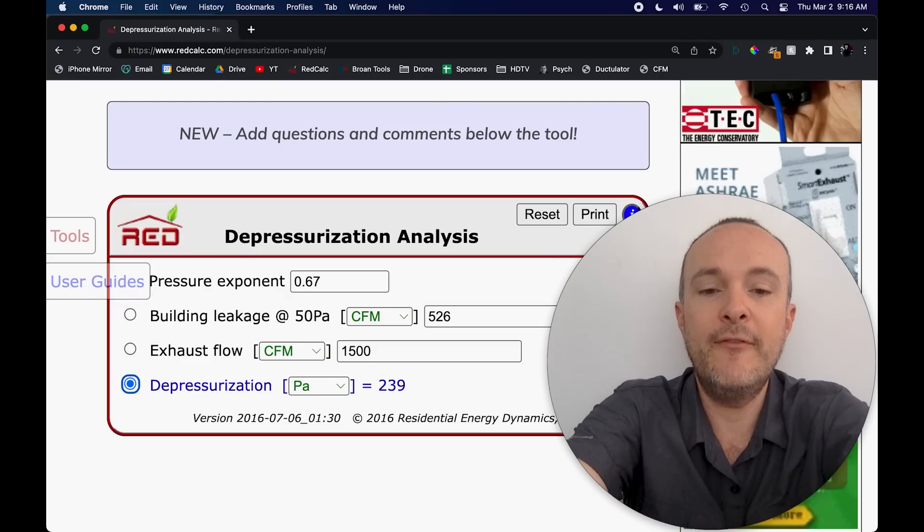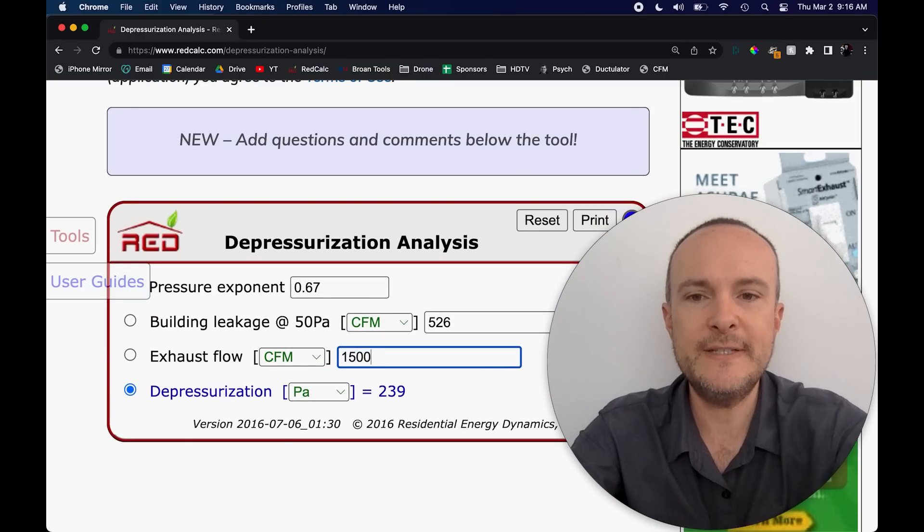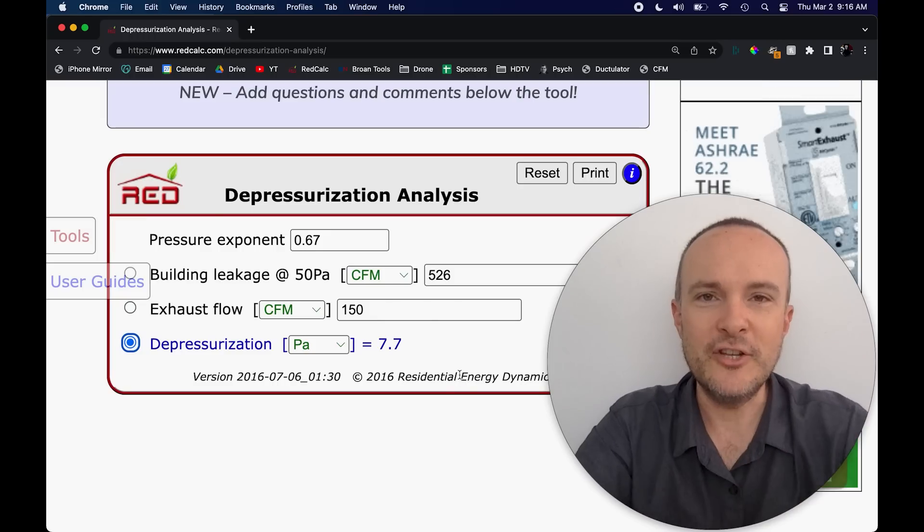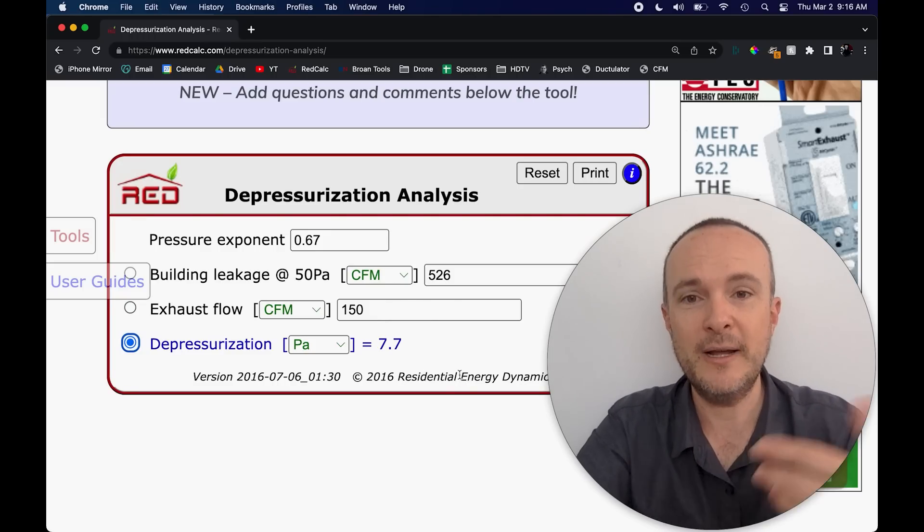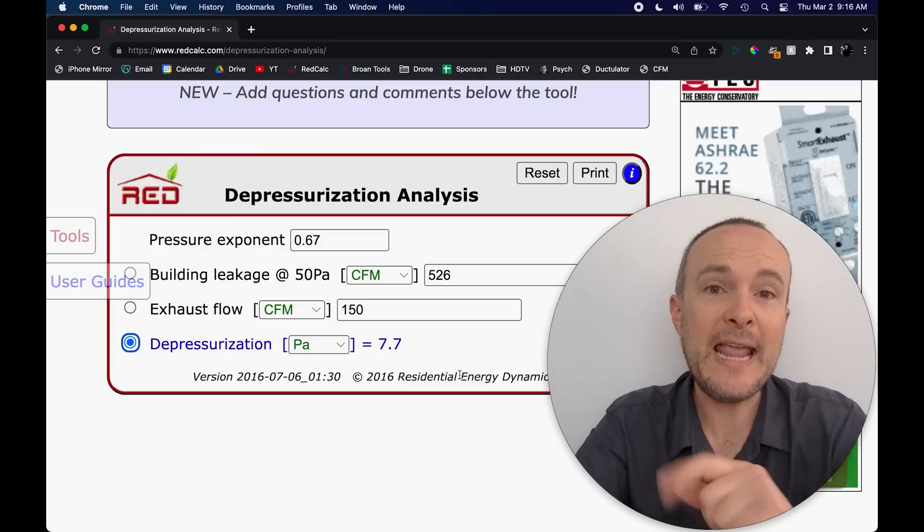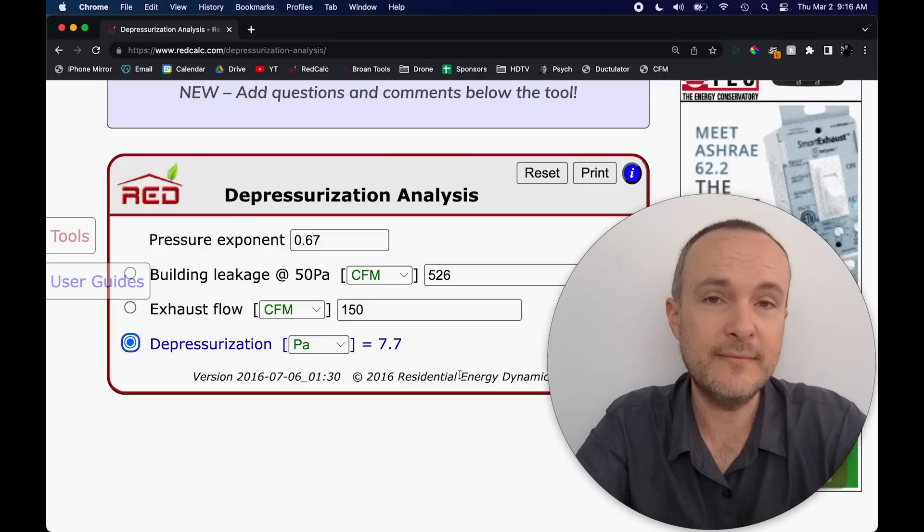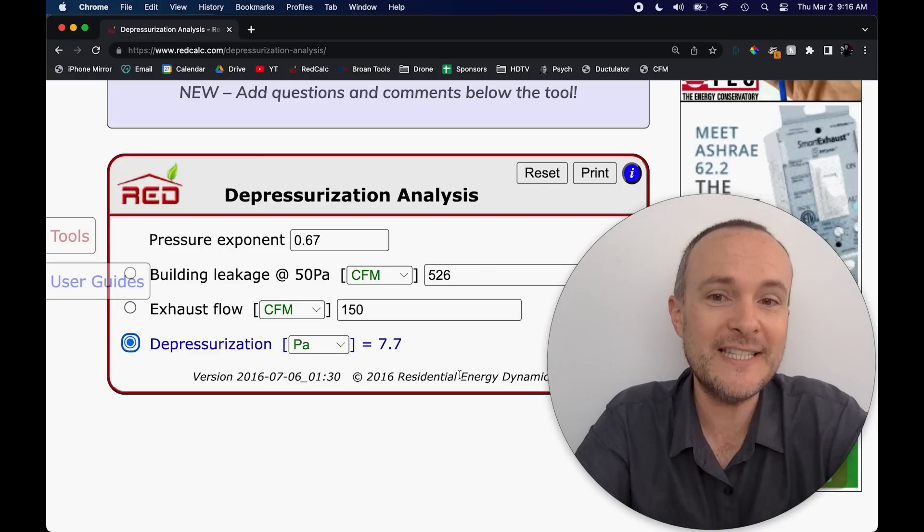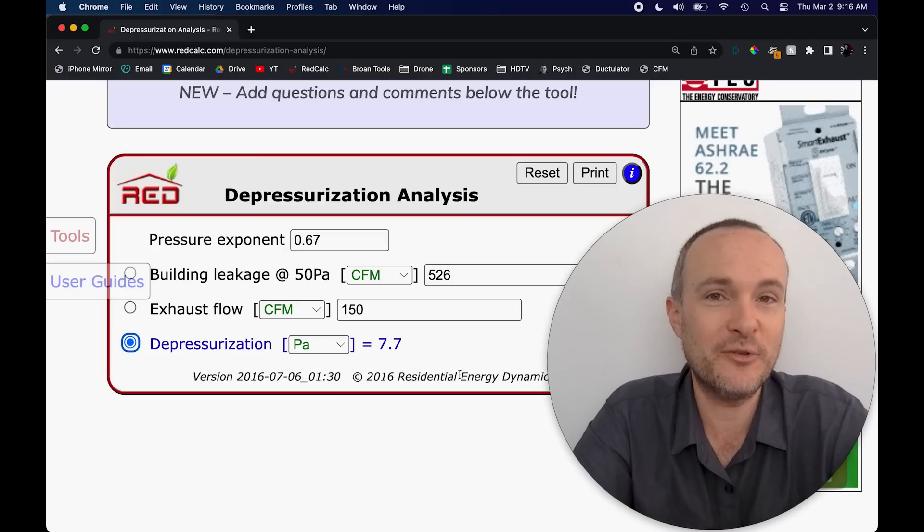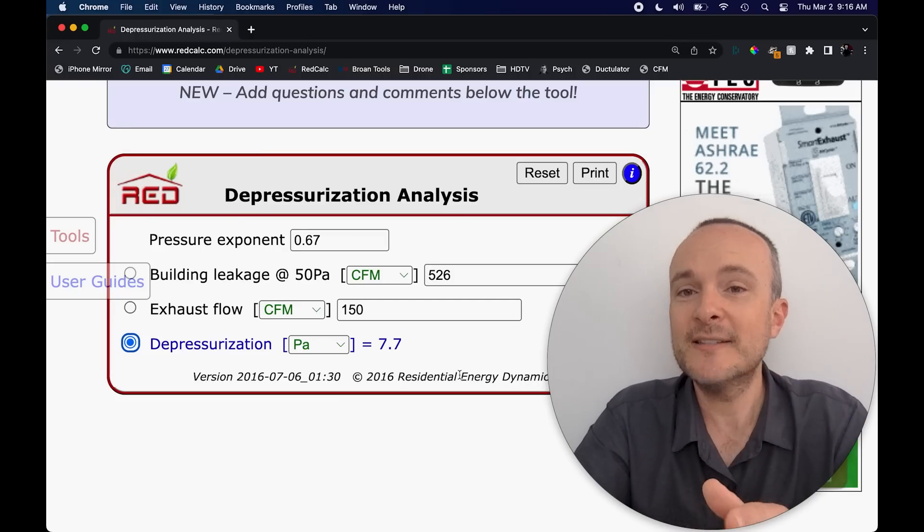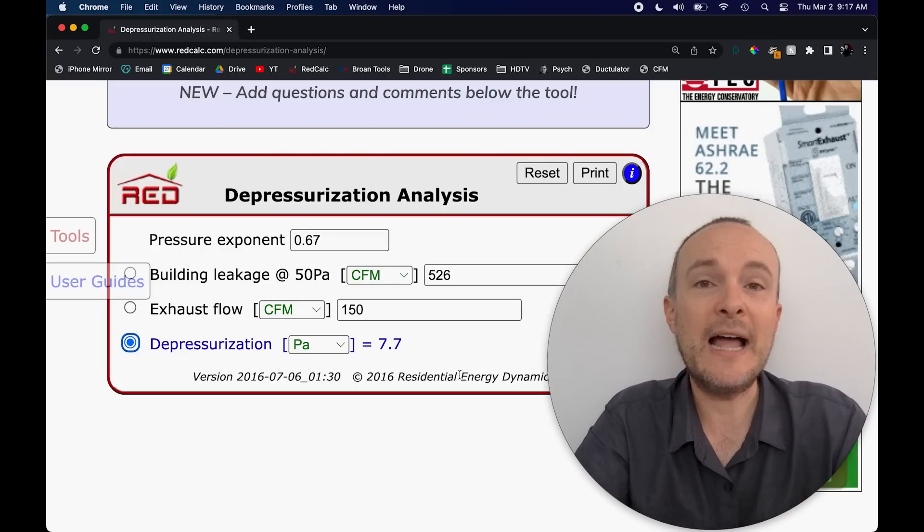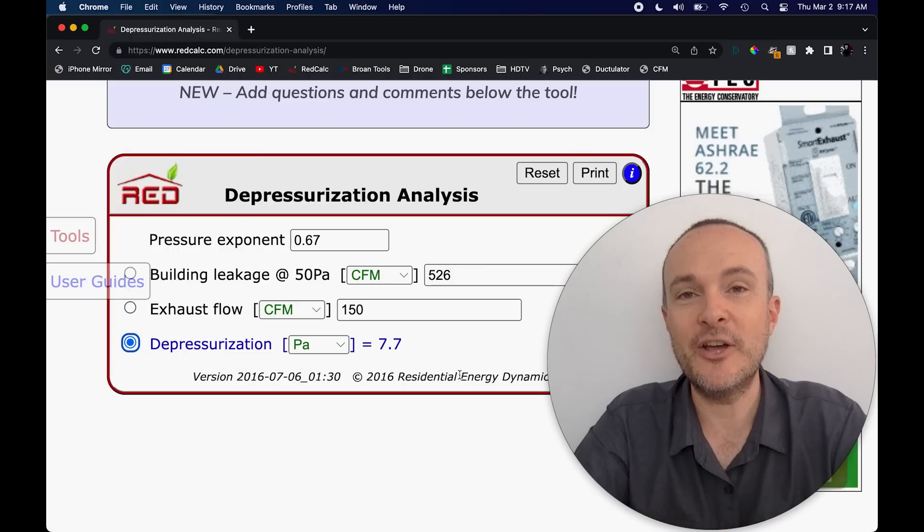Let me just make one last point here, which is vented dryers. If I have a 150 CFM vented dryer, if you're subscribed to this channel, you saw my interview with Scott True, who's my longtime buddy and client, who's building spec homes in Texas. And he had this problem with a vented dryer not venting properly because it couldn't get out because it was depressurizing this house to seven and a half Pascals. And you just can't create a vacuum. Nature will not allow you to do that. So if you're going to use vented dryers, you've got to think about this again, right? And you got to add that into your calculation. That's why I like heat pump dryers.